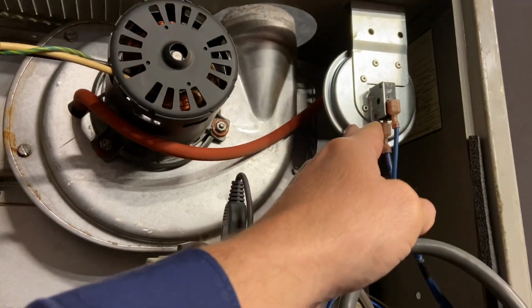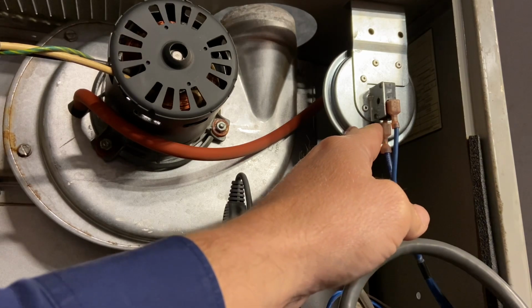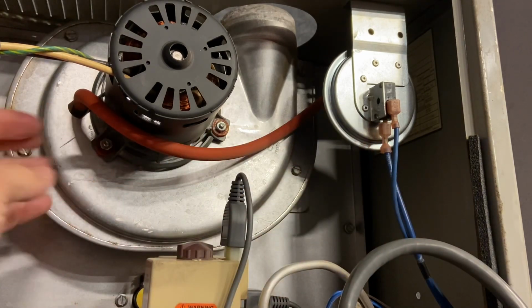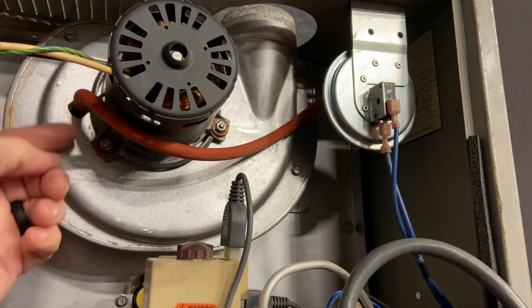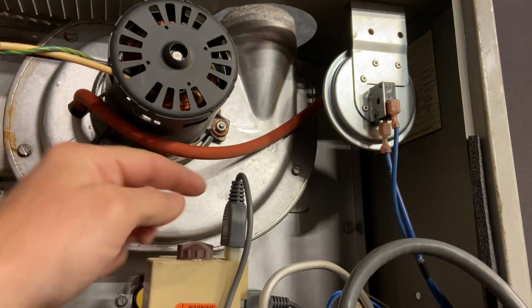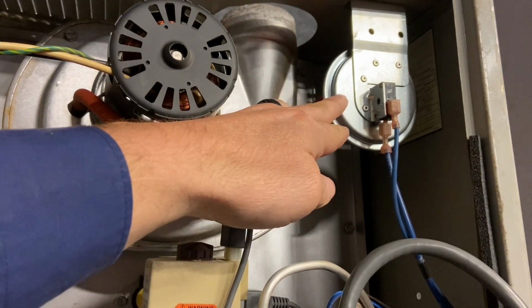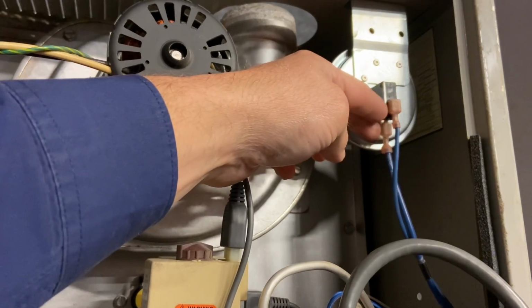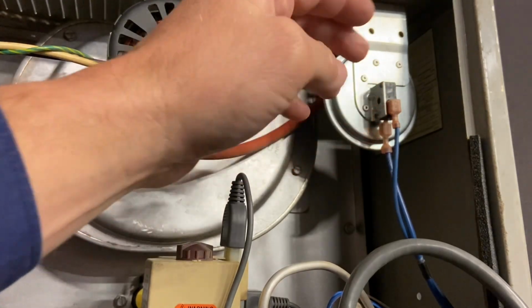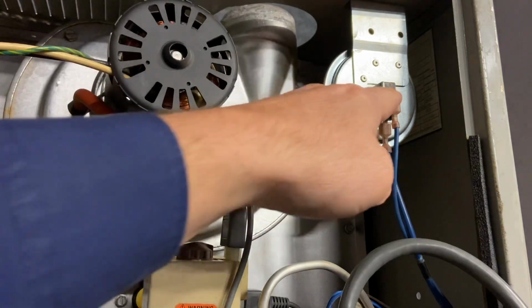On the side here is our vacuum pressure switch, or negative pressure switch. The inducer fan motor pulls a draft through the heat exchanger, negative pressure. It's also pulling a draft through this tube to our pressure switch. It's normally open. These two wires close when this fan is running, it pulls a vacuum and the switch closes.